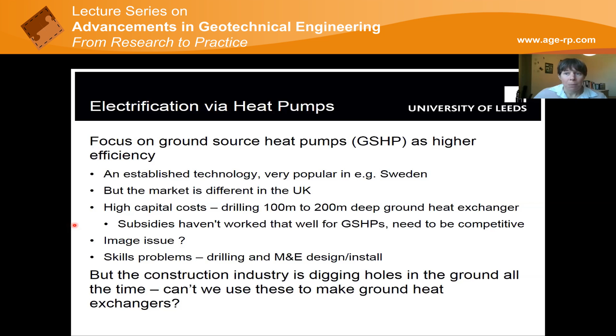An energy pile is where you take a normal pile and embed plastic heat transfer pipes in it, connecting it to your ground source heat pump system so you can exchange heat with the ground. You can store heat there in the summer when cooling your building, and take it out again in the winter when you need to heat it.